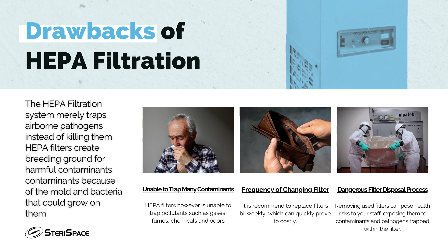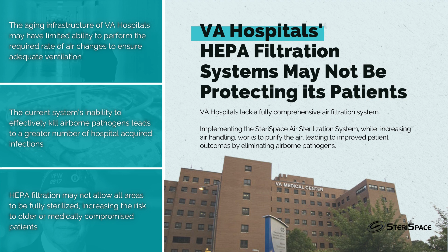HEPA filters need frequent replacement, resulting in high operating costs. When filters are replaced, it's recommended that the technician suit up to protect themselves. And how often does that happen? And is it possible for harmful pathogens to be reintroduced back into the air when the filters are replaced? The VA hospitals are of particular concern when it comes to indoor air quality because of the aging infrastructure. Maintaining the required air changes per hour may be compromised, in addition to inadequate maintenance of air purification systems to maintain continued efficiency and efficacy. This, of course, causes concern for hospital-acquired infections, especially among the elderly and the medically compromised patients.